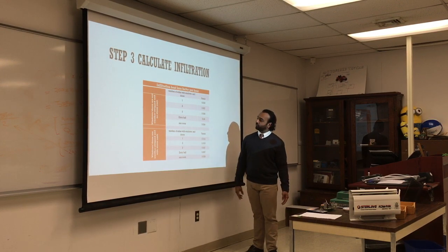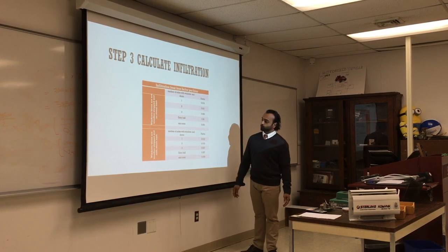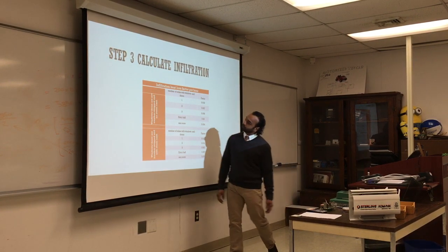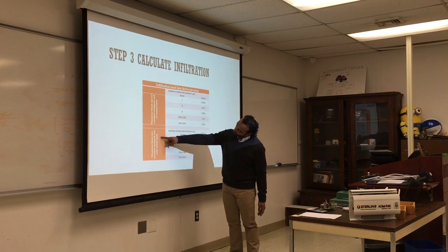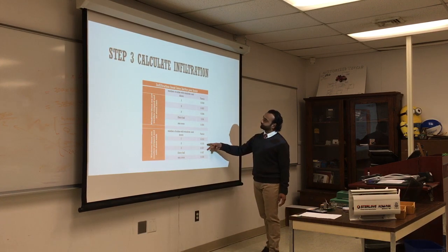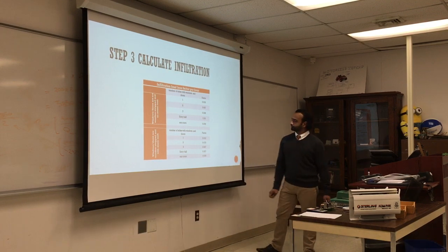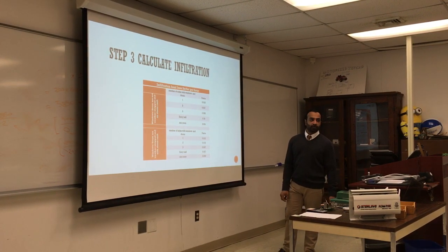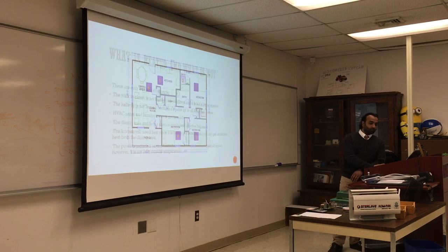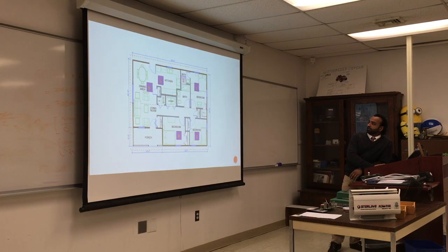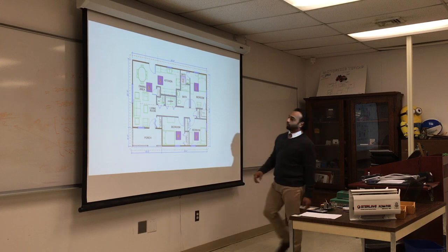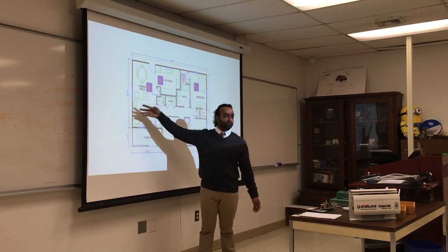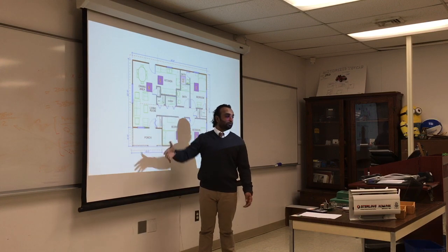Sunrooms, 0.054. So we're going to use, this is with or without? This is with storm sash, we're going to use this one. Does that entry hall assume that it goes right into a hallway, not a room? Yeah. If we look into the floor plan, we don't have an entry hall here, but if we have a big door in here, or on this side, you're going to open the door and all the cold air will come in.